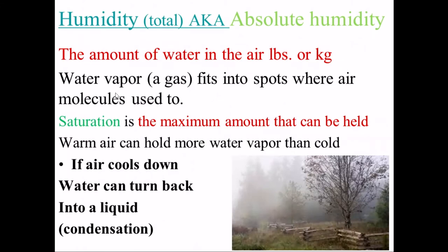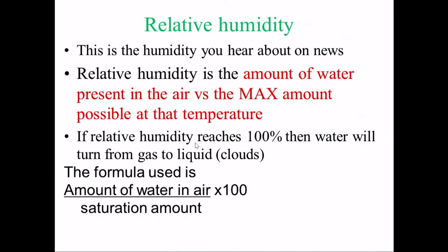Let's talk about humidity. It's tricky, because there's more than one type of humidity. There's absolute humidity and there's relative humidity. Absolute humidity is a basic measurement of how much actual water is in the air — how many kilograms or pounds of water is vaporized in the air. Saturation is the maximum amount of water that can be held in air at certain temperatures. The higher the temperature of the air, the more water it can hold; the colder the temperature, the less water it can hold. Relative humidity is a percentage — what percentage of the maximum amount of water is actually present in that air.